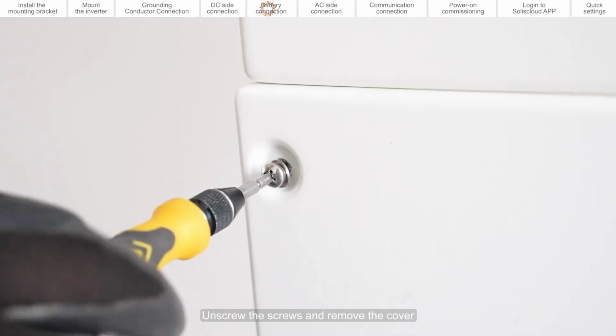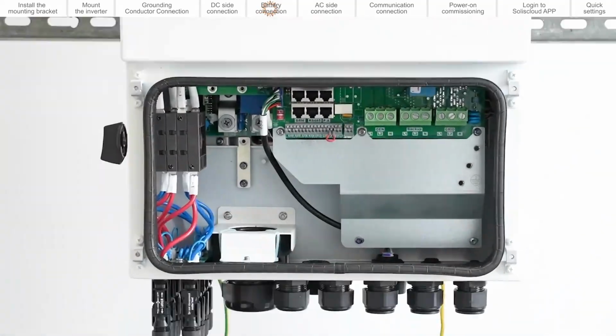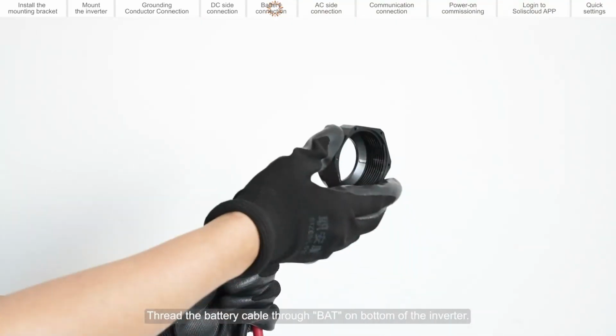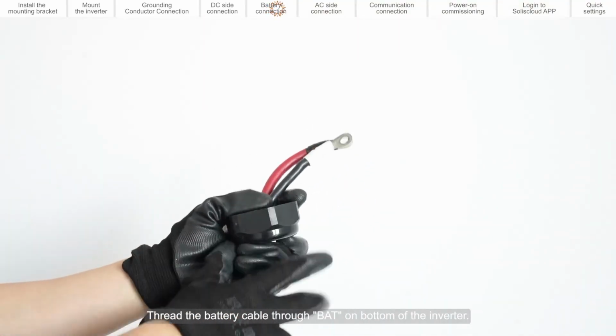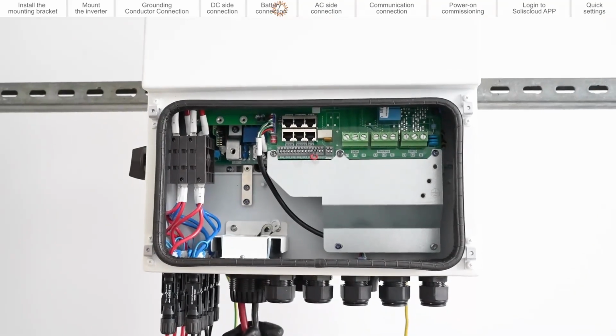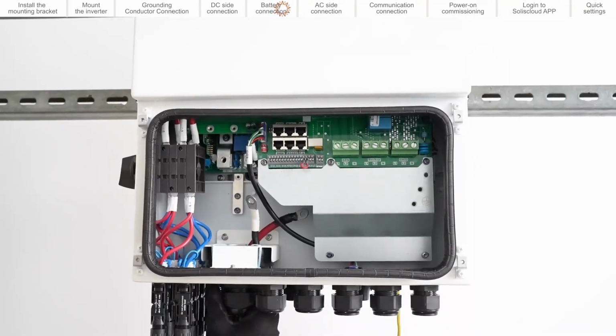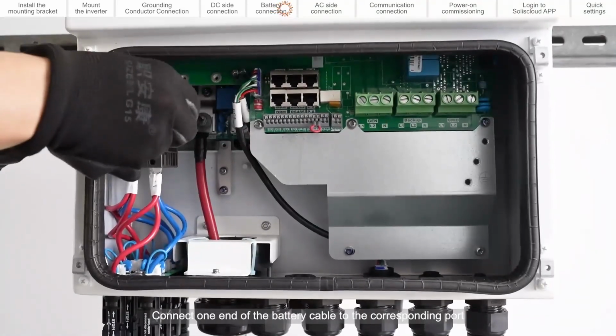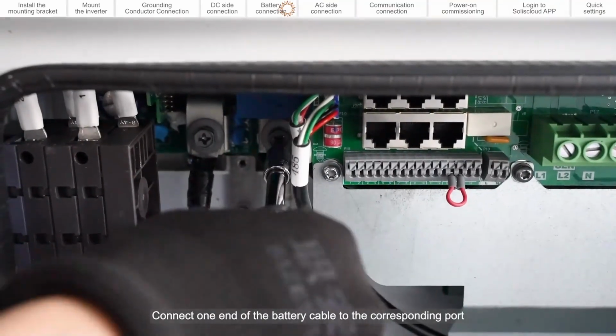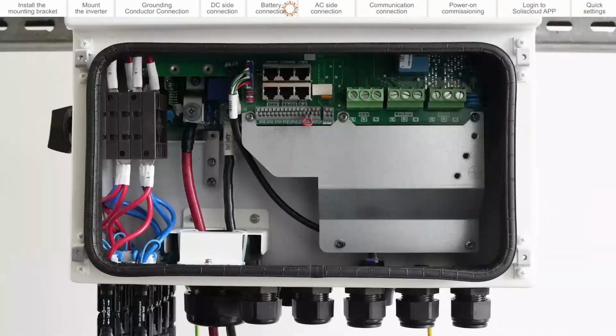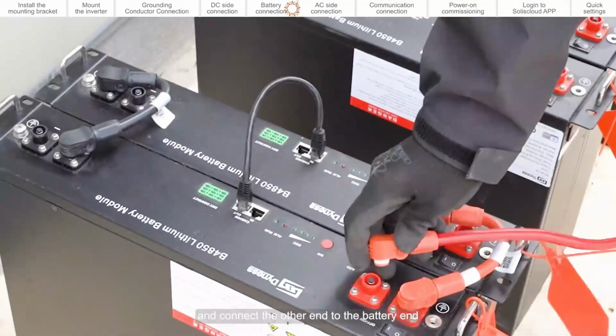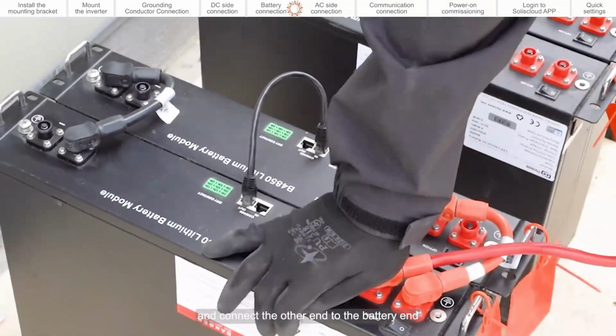Unscrew the screws and remove the cover. Thread the battery cable through the BAT port on the bottom of the inverter. Connect one end of the battery cable to the corresponding port and connect the other end to the battery end.